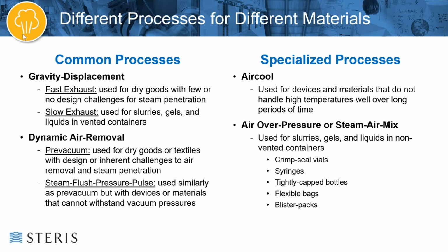And this is used for liquids, gels, and slurries in non-vented containers, such as a crimp cap vial, or syringes, or a bottle with the cap tightly screwed on, flexible bags such as an IV bag, and then blister packs, something that might have a foil lid on it, where the steam can't actually get inside the blister pack. So the steam air overpressure works very well with these contained non-vented containers, in that it allows the materials to be processed without essentially exploding.